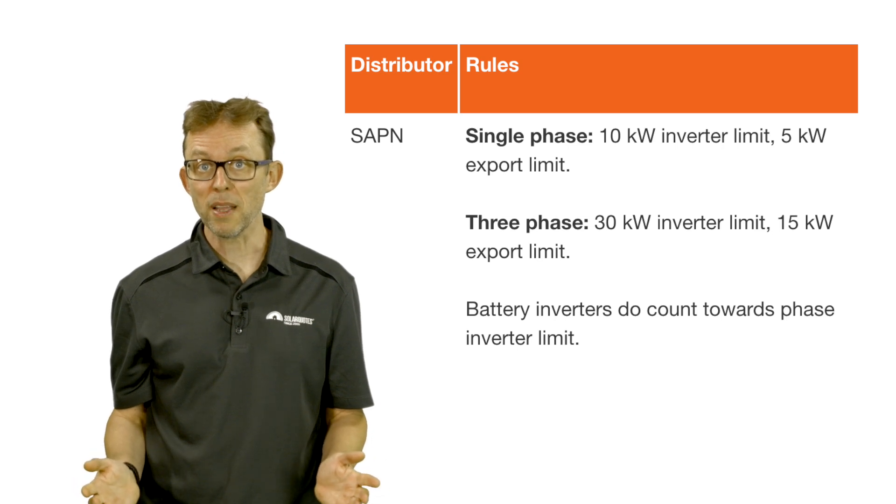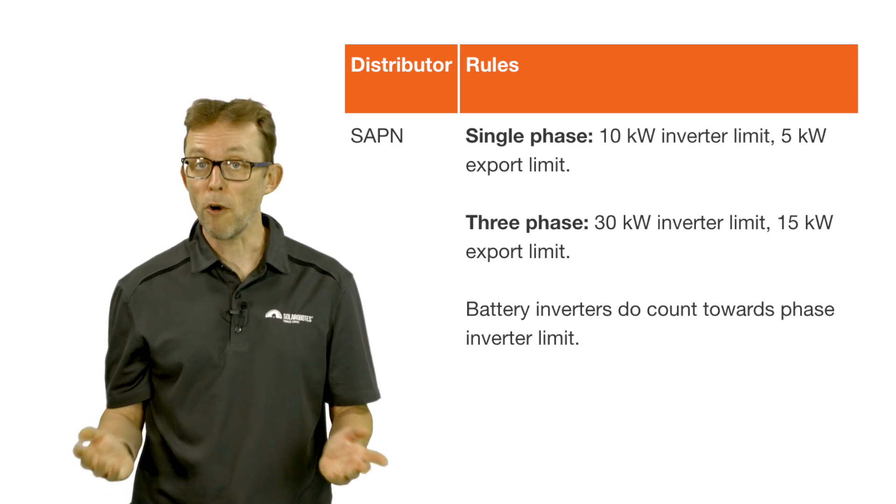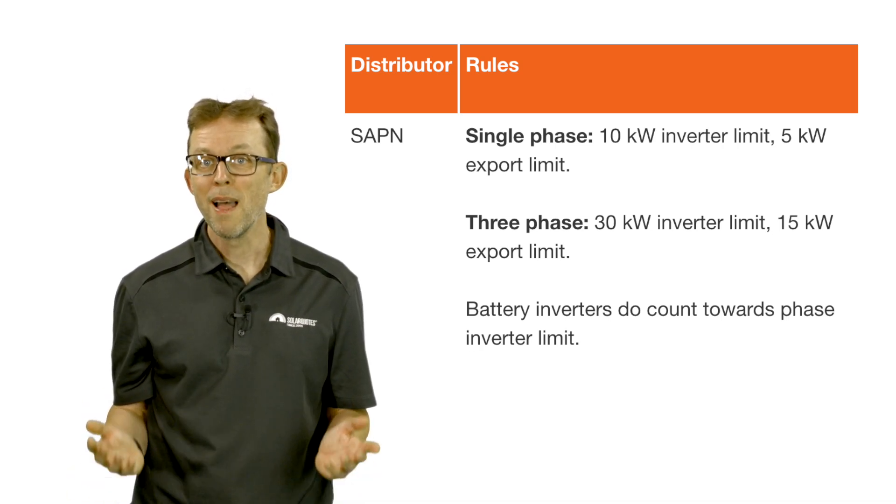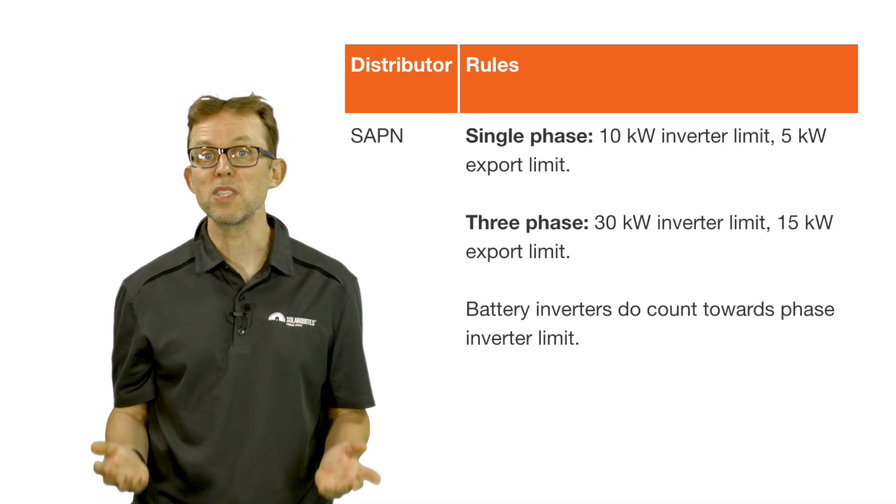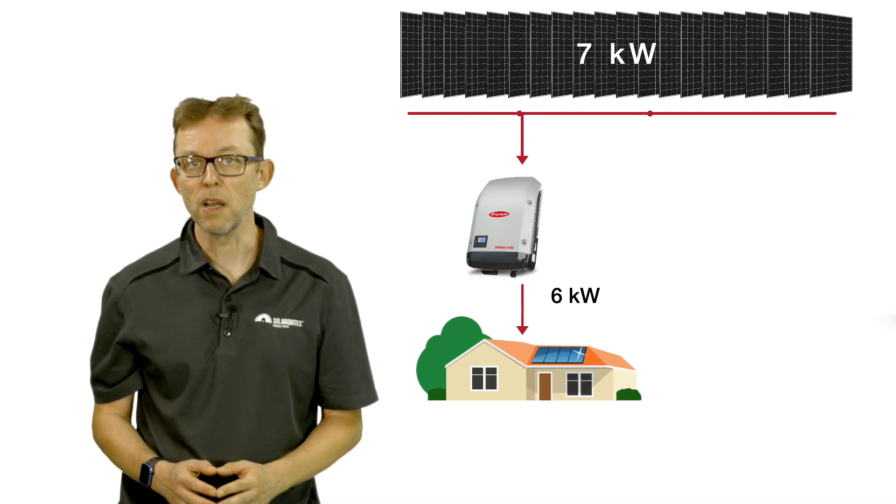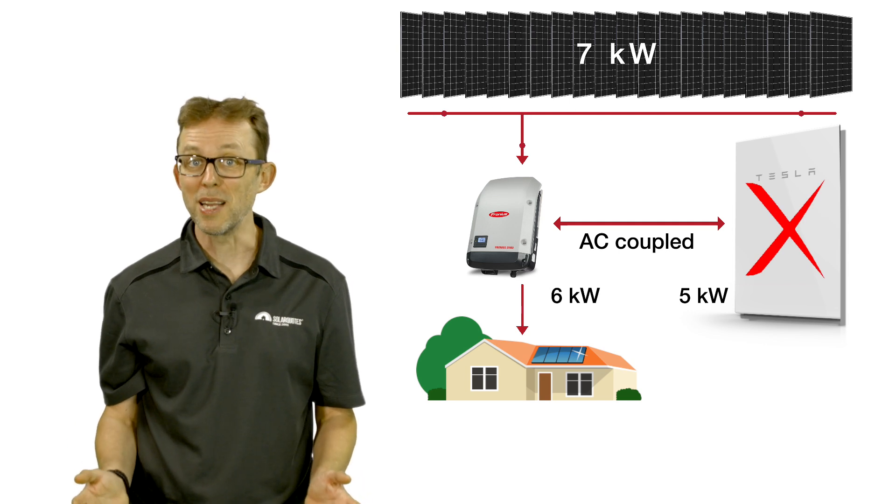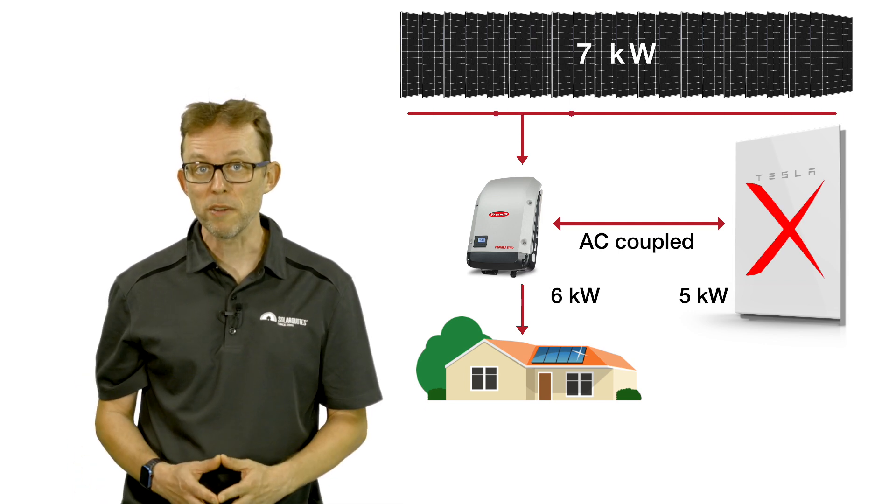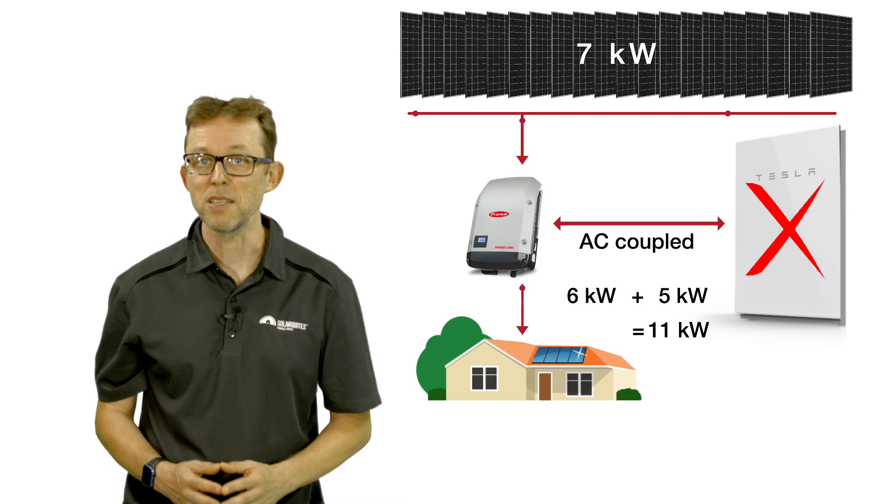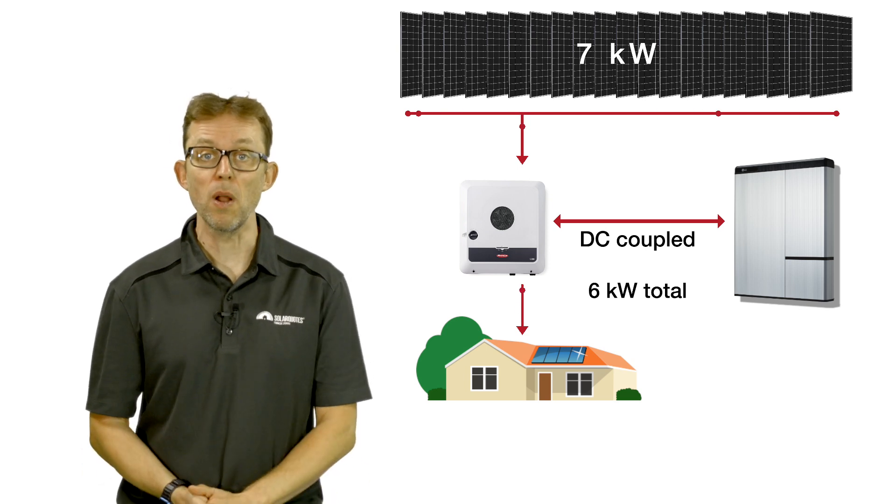Another drawback of AC coupling is rules on system sizing from your local electricity network and they may limit what you're allowed to install. For example, SA Power Networks allows a maximum of 10 kilowatts of inverter capacity per phase. Unless you can get an exemption, they count battery inverters towards this 10 kilowatt limit. Let's say you have an existing 7 kilowatt solar system with a 6 kilowatt inverter. You want to add a Tesla Powerwall which has a 5 kilowatt inbuilt battery inverter. SA Power Networks may say you can't because the 6 kilowatt solar inverter plus the 5 kilowatt Powerwall battery inverter equals 11 kilowatts of total inverter capacity. DC coupling bypasses this limit because there's only one inverter that handles both the battery and solar.